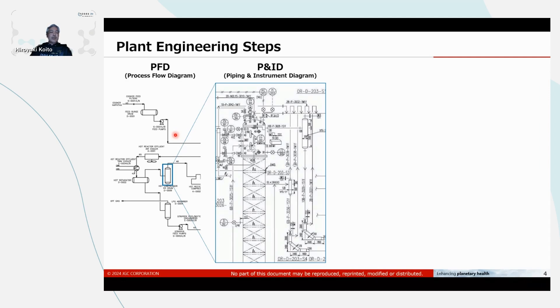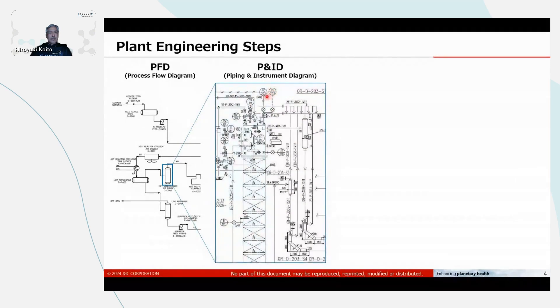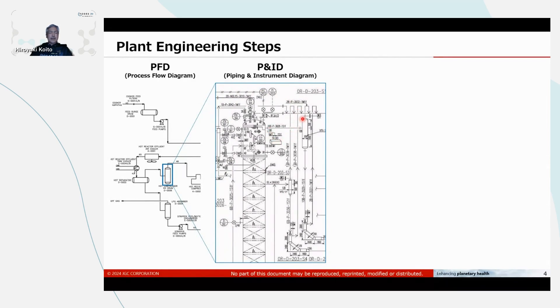Based on this, we develop P&ID — that is piping and instrument diagram. For example, this small area will be developed like this. This big one is equipment, and each line with an arrow is piping, and this balloon — a circle — is an instrument controlling the plant. This another type of line is a signal, wire cables. So this is a detailed diagram, but it's still non-dimensional, and it shows the relationship between equipment, piping, and instrument.